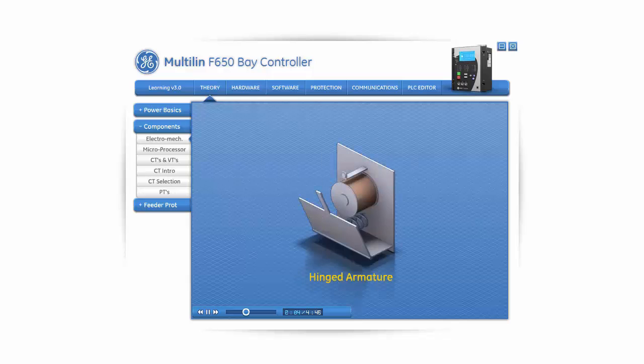The hinged armature construction, which also includes the cantilever and beam type of construction, consists of a flat plate or bar type of armature, which pivots at a fixed point when attracted to the pole face of an electromagnet. The armature carries the moving portion of the contact, which meets a fixed contact when the armature is picked up.